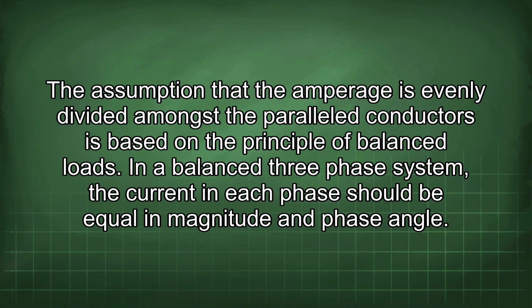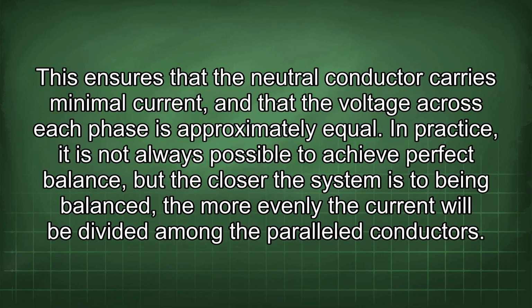The assumption that the amperage is evenly divided amongst the paralleled conductors is based on the principle of balanced loads. In a balanced three-phase system, the current in each phase should be equal in magnitude and phase angle. This ensures that the neutral conductor carries minimal current and that the voltage across each phase is approximately equal. In practice, it is not always possible to achieve perfect balance, but the closer the system is to being balanced, the more evenly the current will be divided among the paralleled conductors.